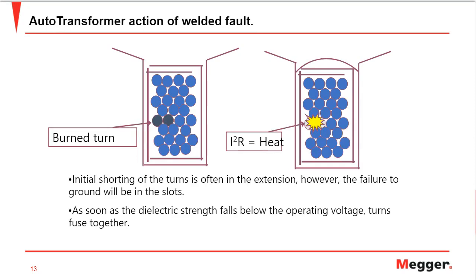The normal current would be 16 times more, and the heat would be the square factor of 16, which is 256 times more, which is a lot for the motor to handle. And according to IEEE, the welded fault turns would burn through slot liner to ground within 15 minutes. So that's pretty quick once it experiences the welded fault. We'll see a picture.